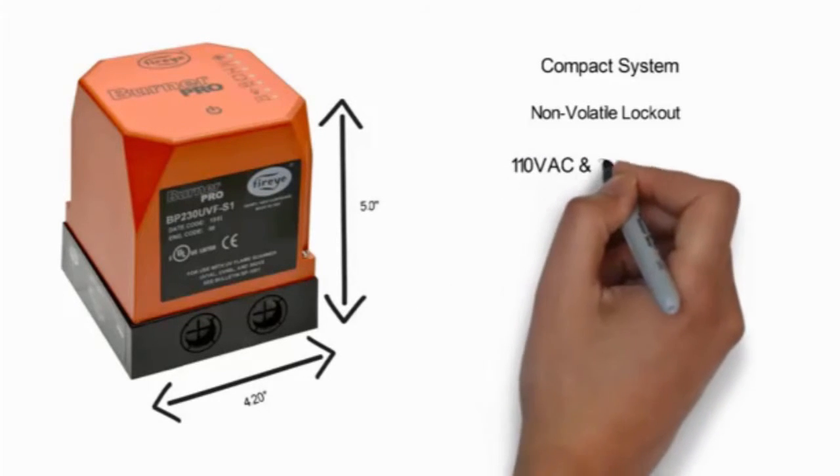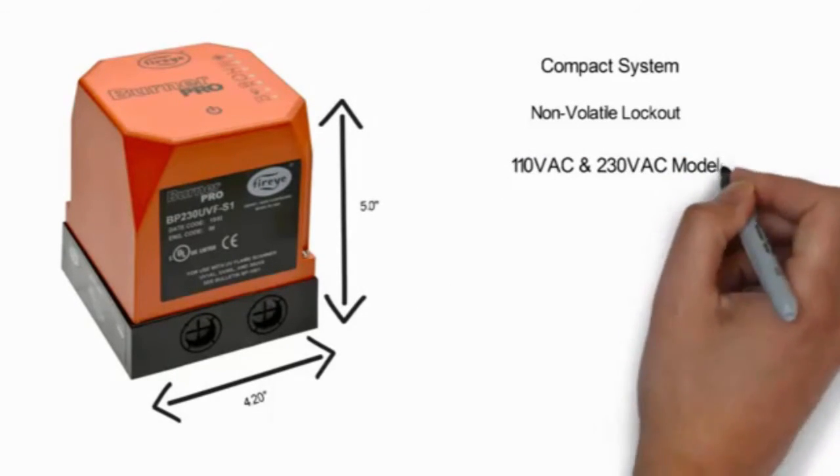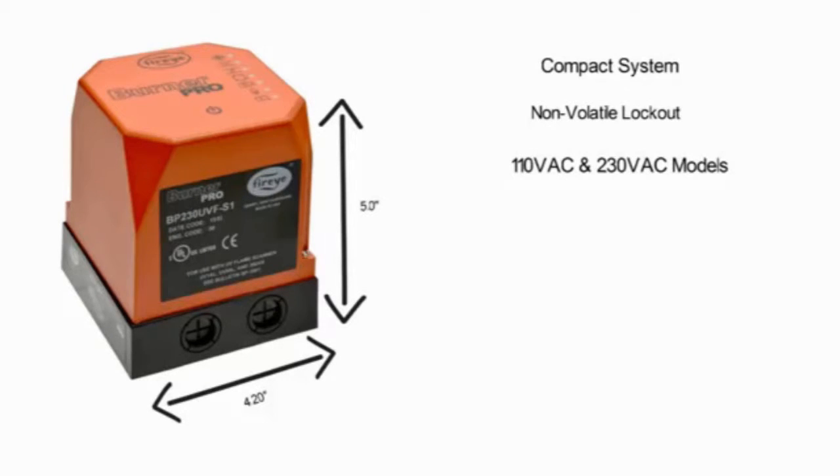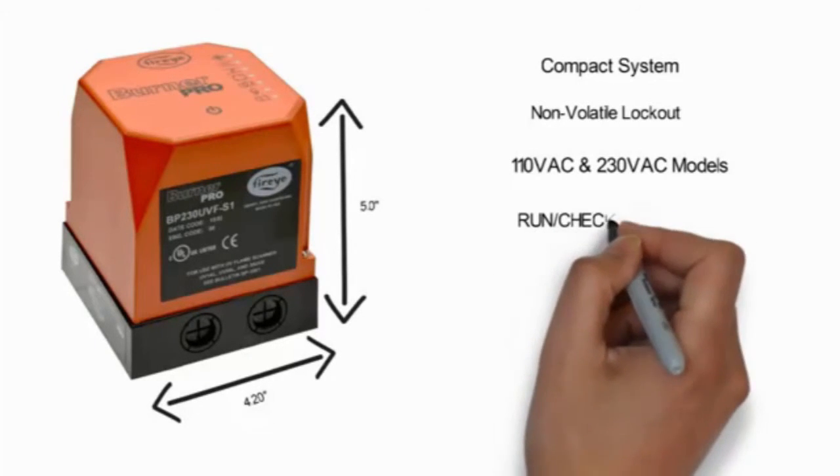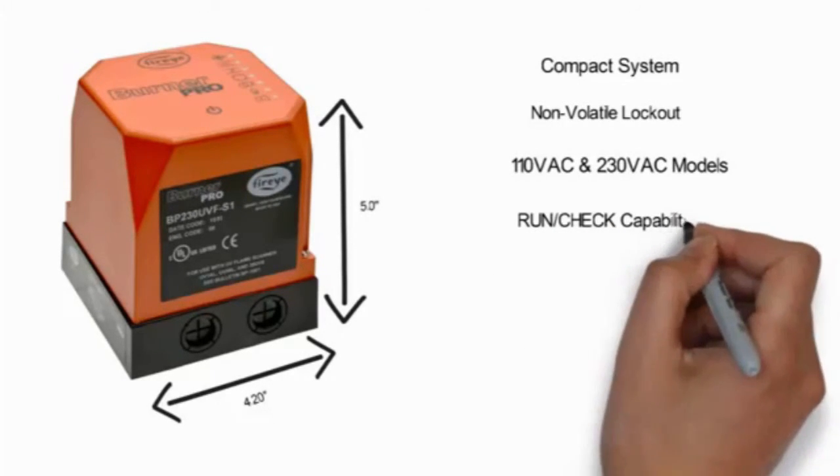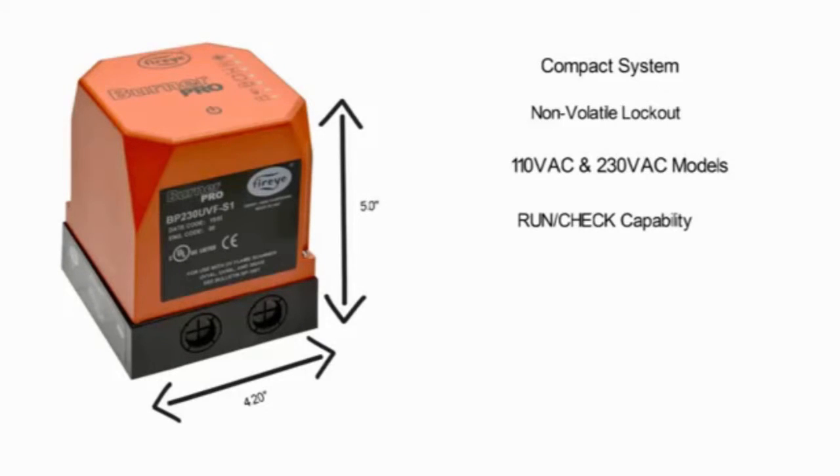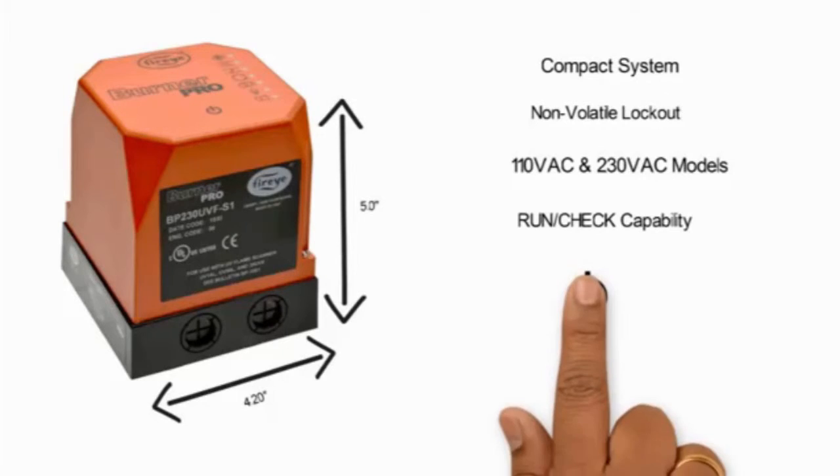110 VAC and 230 VAC models available for greater flexibility in your application. Run check capability allows the system operator to stop the program sequence in the purge, ignition, PTFI and MTFI positions during system commissioning.